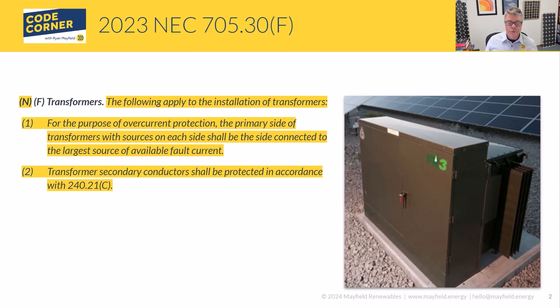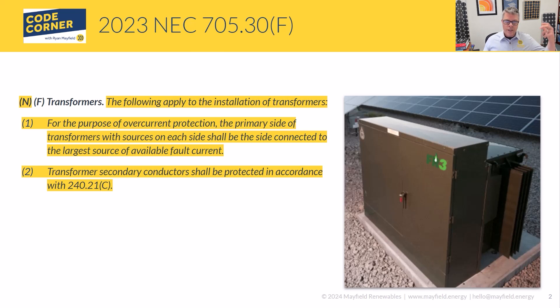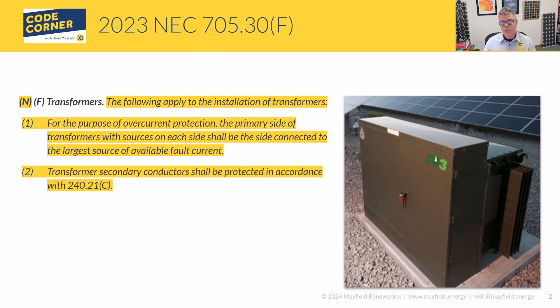For the purpose of understanding this code, we're going to call the utility side the primary side and the solar side the secondary. That can get a little confusing because in this scenario the inverter/solar side is 480V and the utility side is 208V — so the primary side would be the lower of the two voltages and the secondary would be the higher. Keeping that in mind with this code definition is an important thing to do.